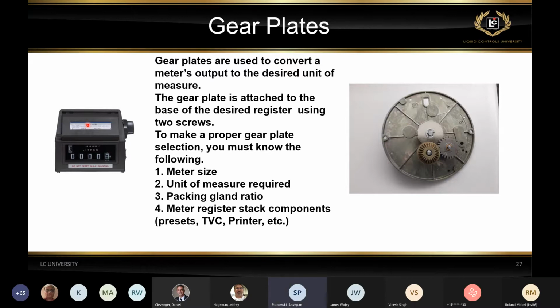And we'll look at different gear plates briefly, but this is one of the more important parts of meters with mechanical registration, making sure that the gear plate is correct, because that gear plate will vary, and it will vary depending on the meter size. So you could have a counter in gallons on an M7 meter, and you could have a counter in gallons on an M60 meter, but they will definitely have different gear plates. So units of measure will also matter. Let's say liters versus gallons, they will have different gear plates. The packing gland ratio will affect the gear plate. They have to match with each other. And also, it depends on which components we are driving. Are we driving only a counter printer, or are we adding other components like a preset, temperature volume compensator, maybe a swivel, and all that will affect the ratio of the gear plate.